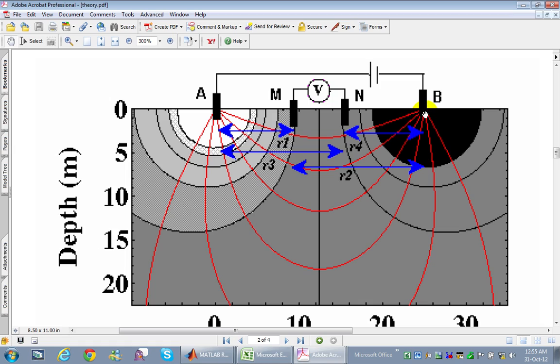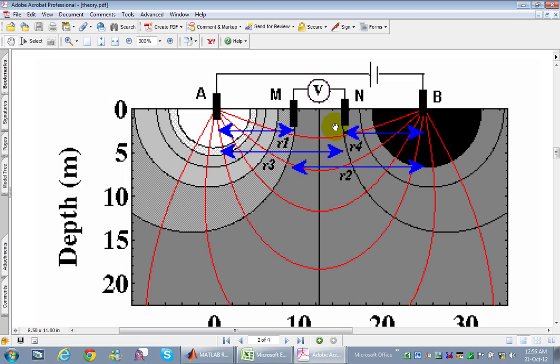Current is injected at electrode A, passes through the earth, and closes the circuit at electrode B. The two inner electrodes are used to measure voltage. By injecting a known current and measuring the voltage drop between the inner electrodes, we can determine the soil resistivity.